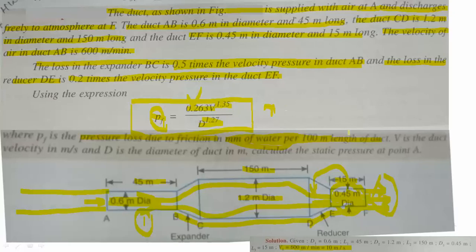The unit of pressure loss from this equation is millimeters of water per 100 meters length. V is the duct velocity in meters per second — velocity must be in meters per second. D is the diameter in meters — we take D in meters only, indicating the diameter of the duct.